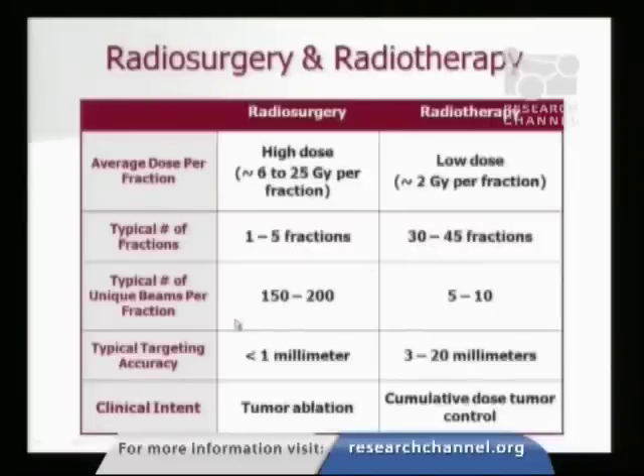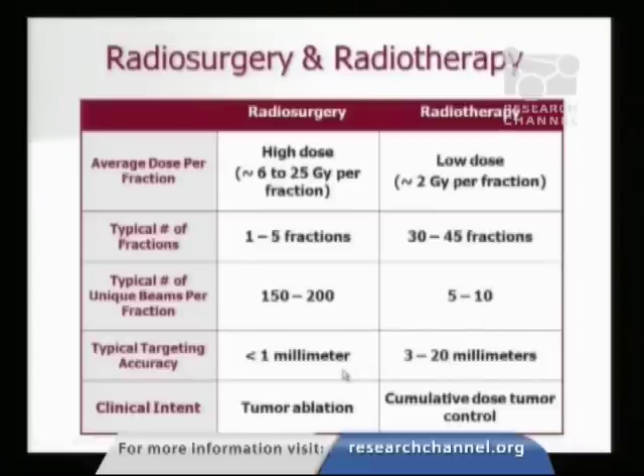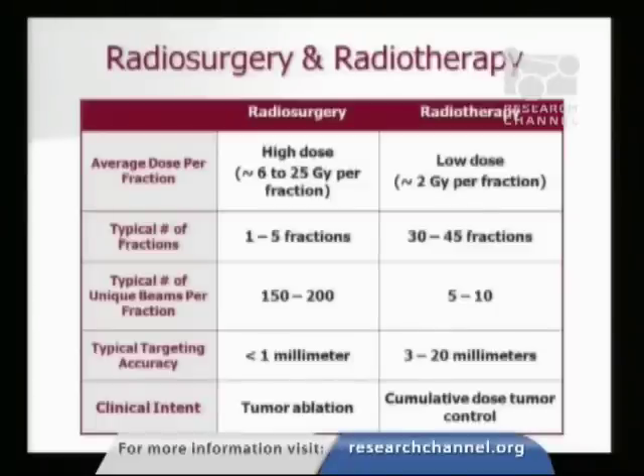The number of beams used is also very different. We use about 150 to 200 beams of radiation with radiosurgery, compared to five to ten beams with conventional radiation therapy. The targeting accuracy allows us to do this — with radiosurgery, targeting accuracy is within one millimeter. Whereas with conventional radiation techniques, because of the bulk of the machines and other features, it may be down to about two millimeters with image-guided techniques, and maybe even up to 20 millimeters with very crude radiation techniques.